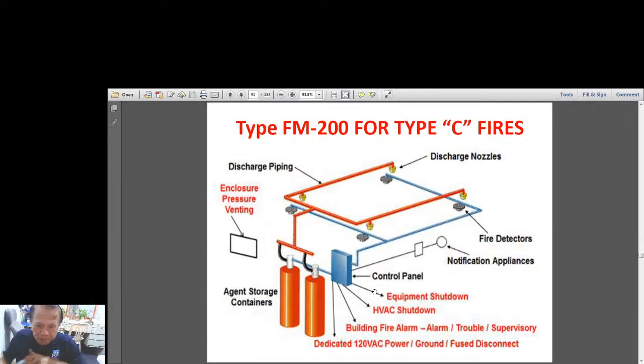Okay, so here you have these two cylinders as the agent cylinder, agent storage containers, these ones. And you have their piping here, the orange piping, and you would have the nozzles here. 4 discharge nozzles, 1, 2, 3, and 4, equally spaced on top of the room that should be protected.